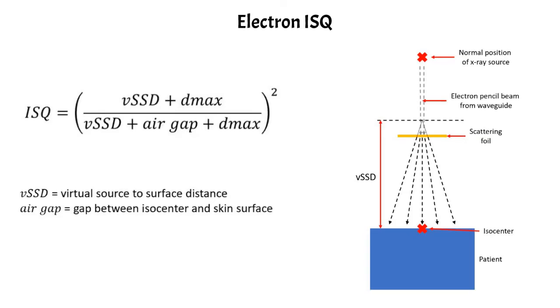And this is always measured with the surface of the phantom placed at the isocenter, which is a normal SSD of 100 centimeters. And so the virtual SSD is what we would actually measure and use when we do our inverse square correction.